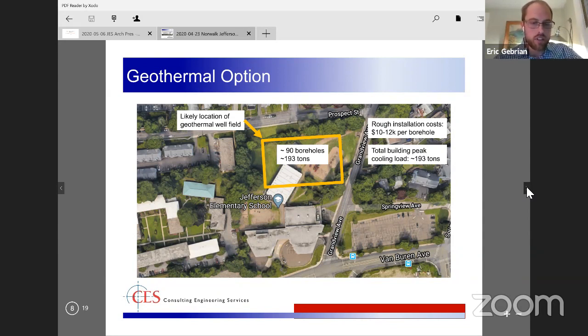Lisa, you can point to the temporary classrooms that are going away. The yellow rectangle roughly represents how much area we would need for these boreholes. We would need to drill about 90 boreholes, spaced about 20 feet on center all over this site, about 500 feet deep, then run pipes over to the building, and cover it all back up with dirt before doing our site work. So a lot of costs associated there - it's roughly $10,000 to $12,000 per borehole. Our total peak building load is about 193 tons.